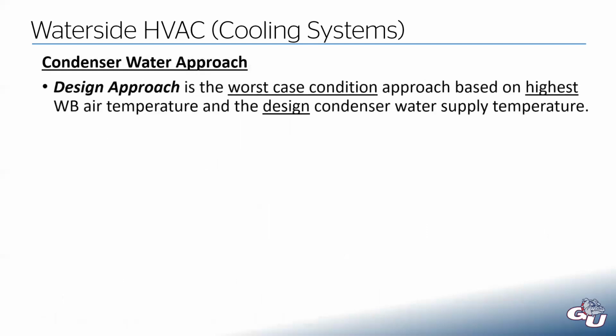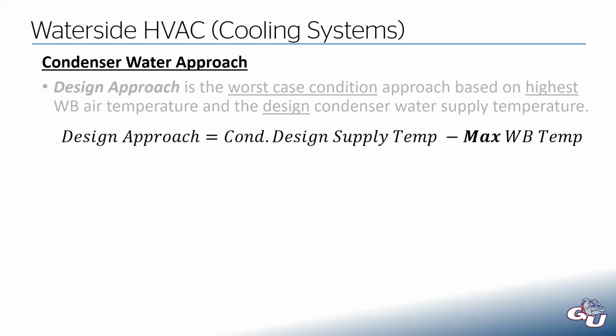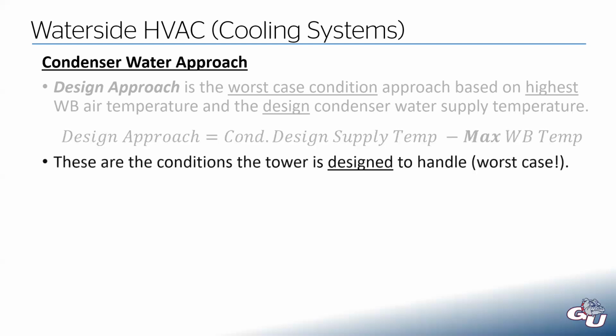The design approach, which I'm referencing as a specific term, the design approach is the worst case condition based on the highest wet bulb temperature we can expect and our design condenser water supply temperature. As a design engineer, this is what I care about. What's my worst case condition? What is my design approach for my cooling tower? So our design approach is our design condenser supply temperature minus our maximum expected wet bulb temperature. That's the conditions the tower is designed to handle. Worst case scenario.